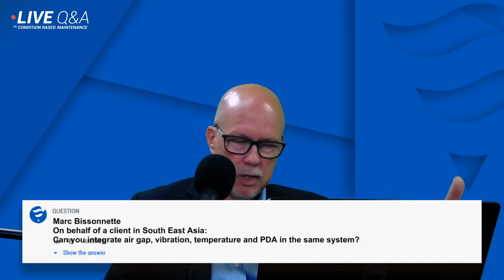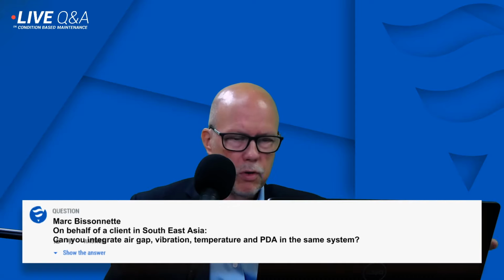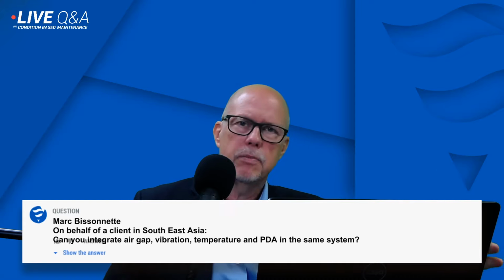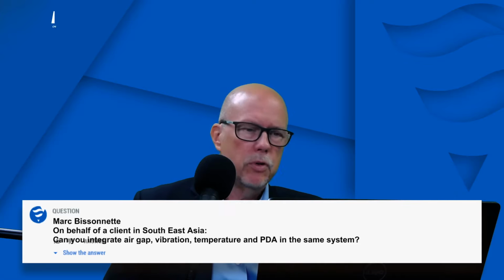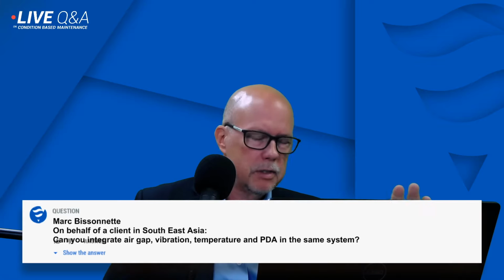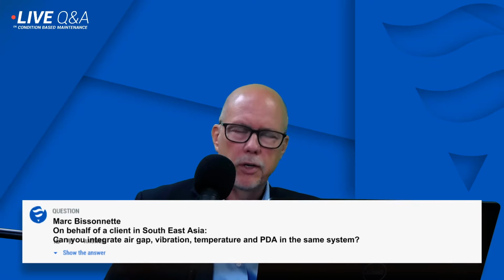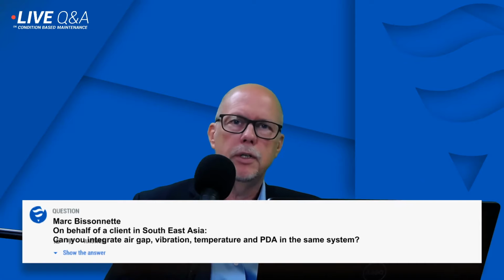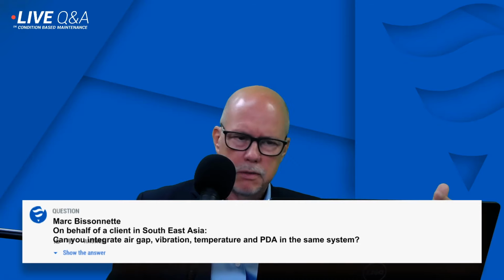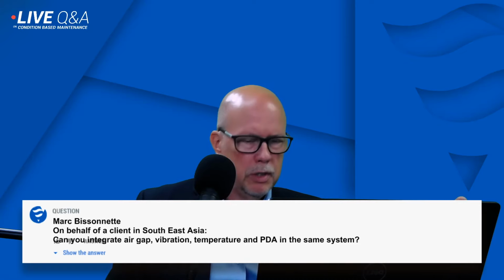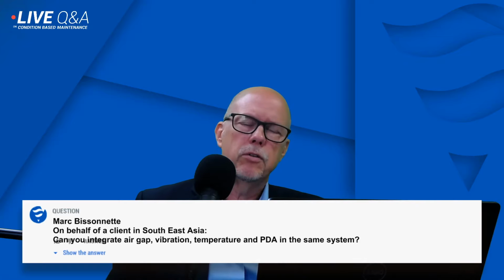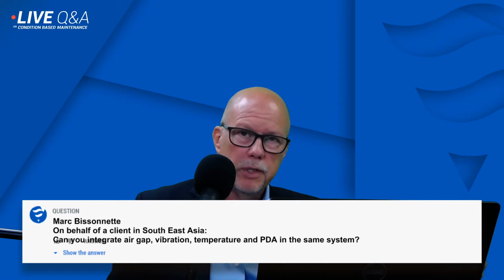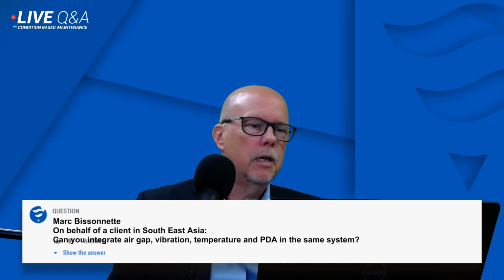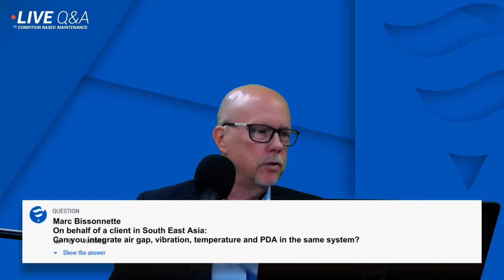So we need all that information. If we can get access to flux, air gap, shaft vibration, core vibration, frame vibration, axial displacement, turbine runner clearance probes, accelerometers on the bearings, temperature probes, pole temperature, interconnection temperature, along with all the auxiliary information, megawatts, megavars, speed, temperature, voltage, rotor and stator current, humidity, all this information can be the important piece necessary to make a correct determination whether there's an issue that needs to be dealt with or not.